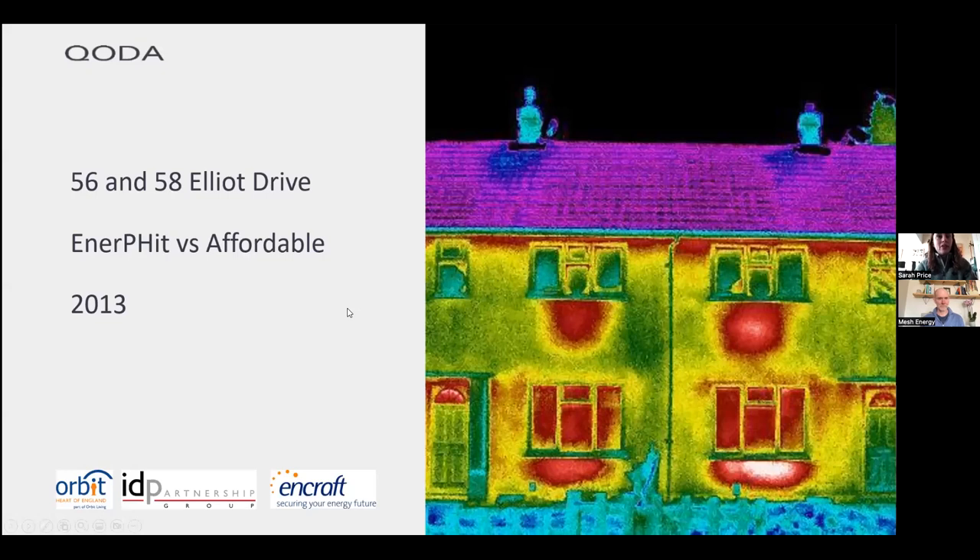The first project I want to talk about was my very first retrofit project, my very first Passive House project. It happened to be a Passive House retrofit and it was a pilot project done by Orbit Heart of England. At the time I was working for Encraft and we also worked with the architects IDP. They really wanted to have a look at what EnerPHit looked like, Passive House retrofit, and whether we could do a more affordable version as well. We took a thermographic image of a pair of semis — no fines concrete, really leaky buildings, very poor airtightness. The red patches under the windows? That's the radiators — you can see where the radiators are from the outside of the building, such is the building fabric's poor performance at keeping heat in.